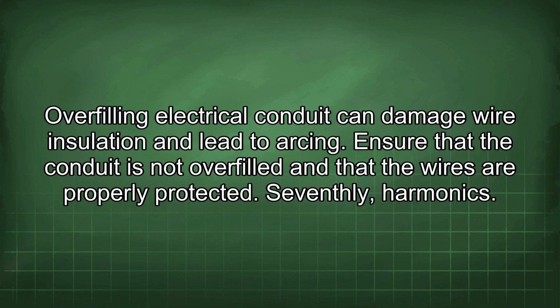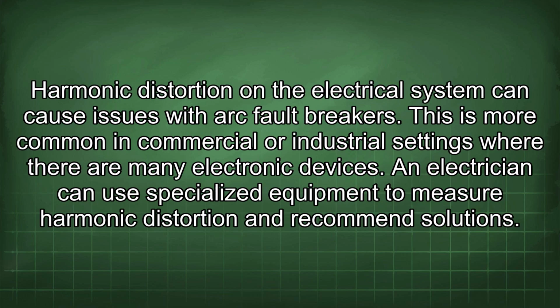Seventhly, harmonics. Harmonic distortion on the electrical system can cause issues with arc fault breakers. This is more common in commercial or industrial settings where there are many electronic devices. An electrician can use specialized equipment to measure harmonic distortion and recommend solutions.